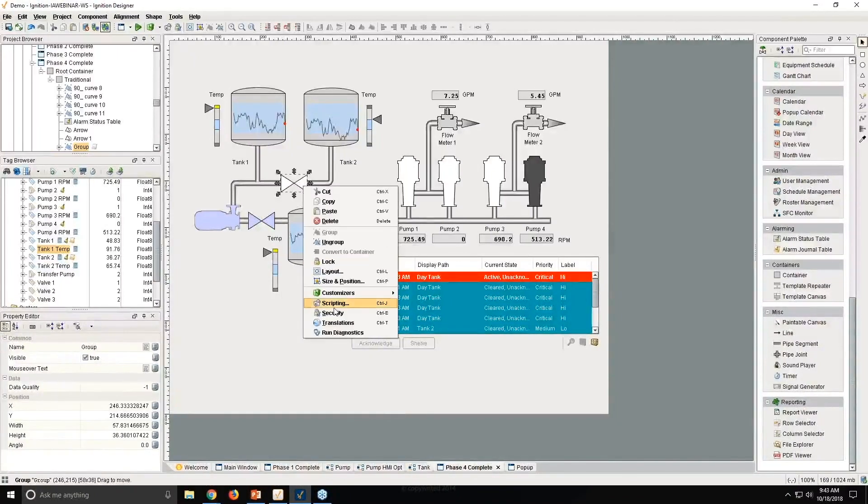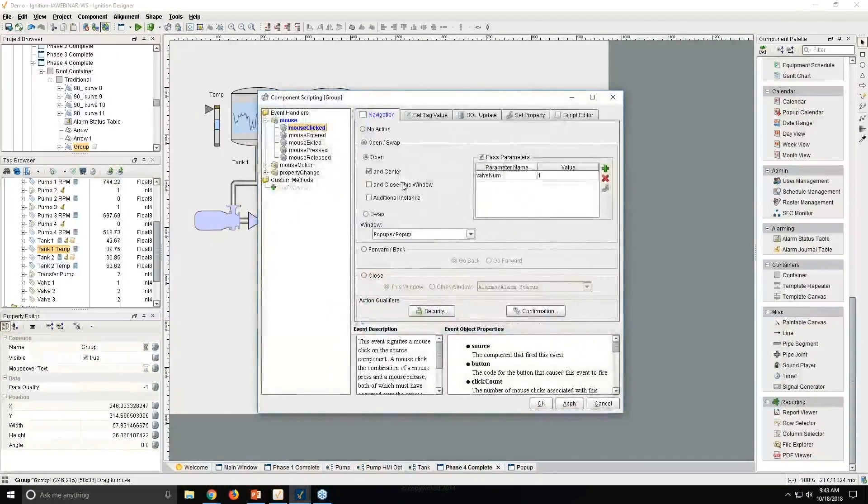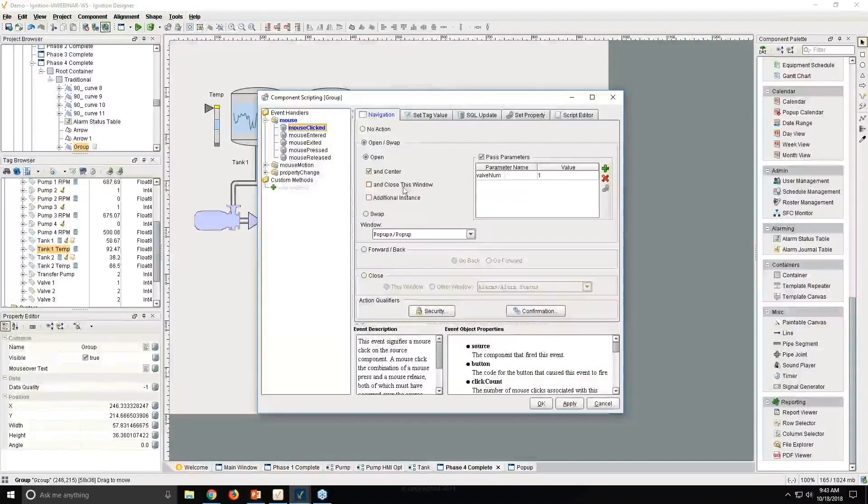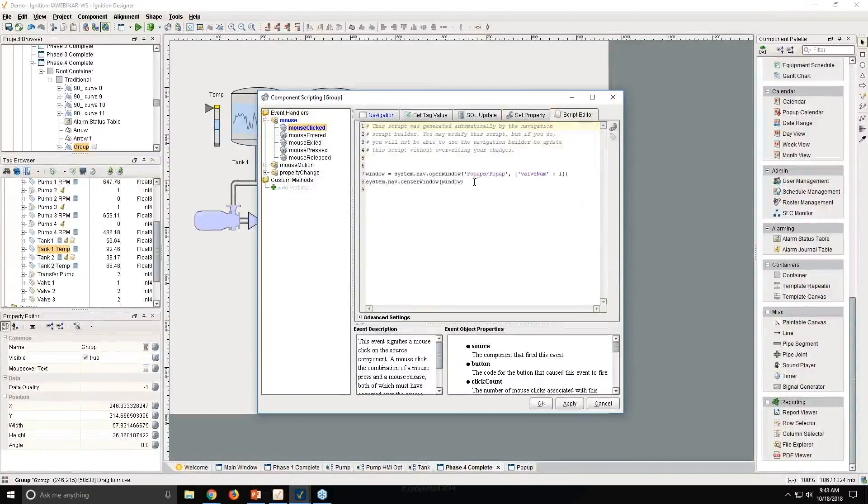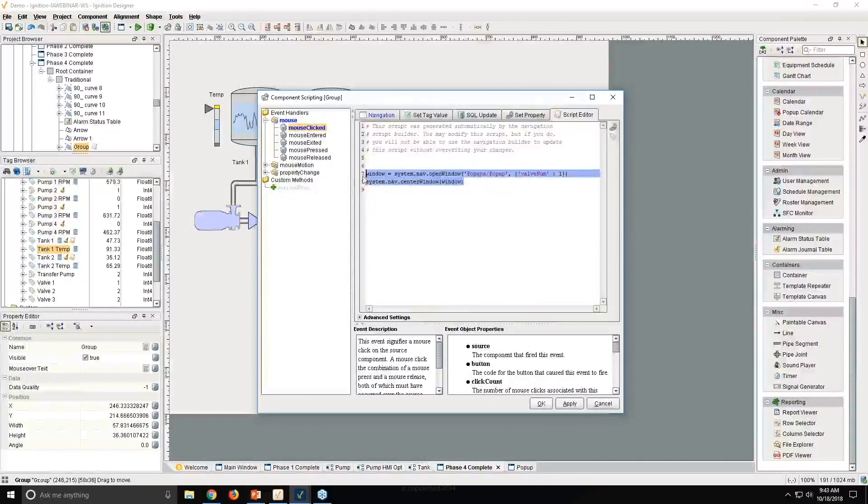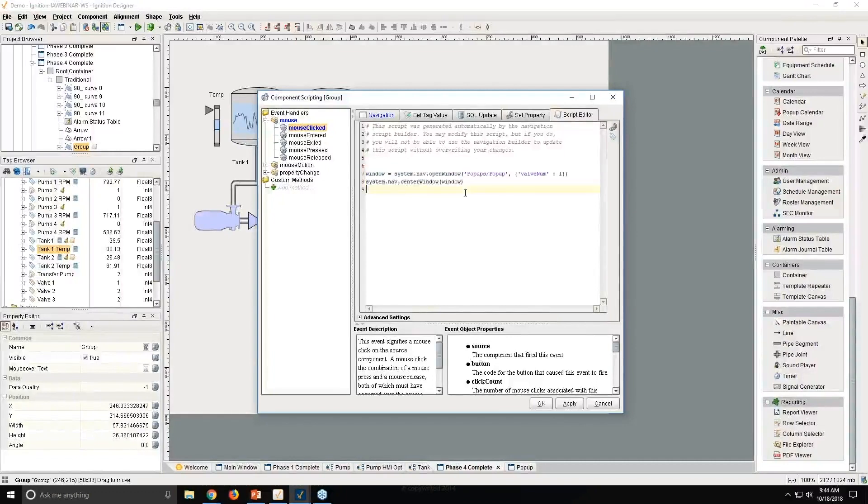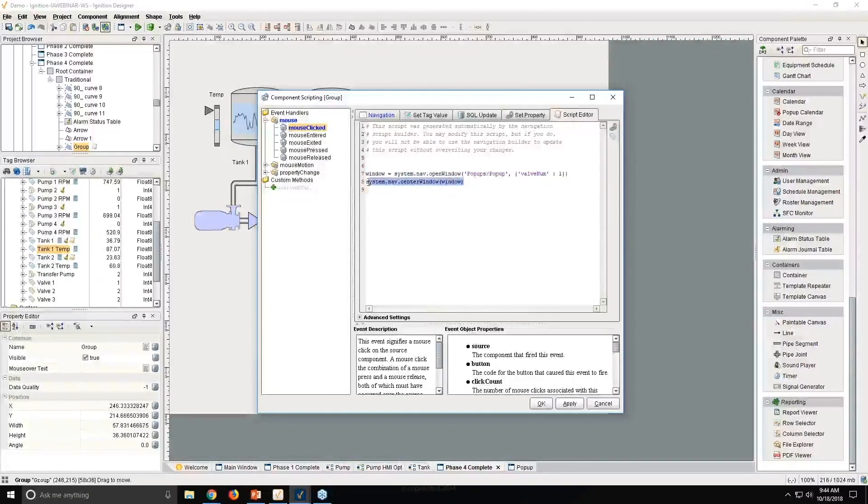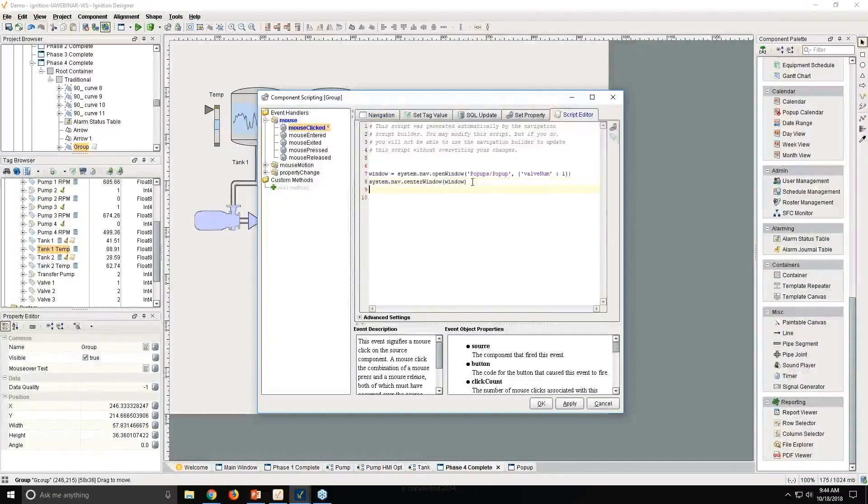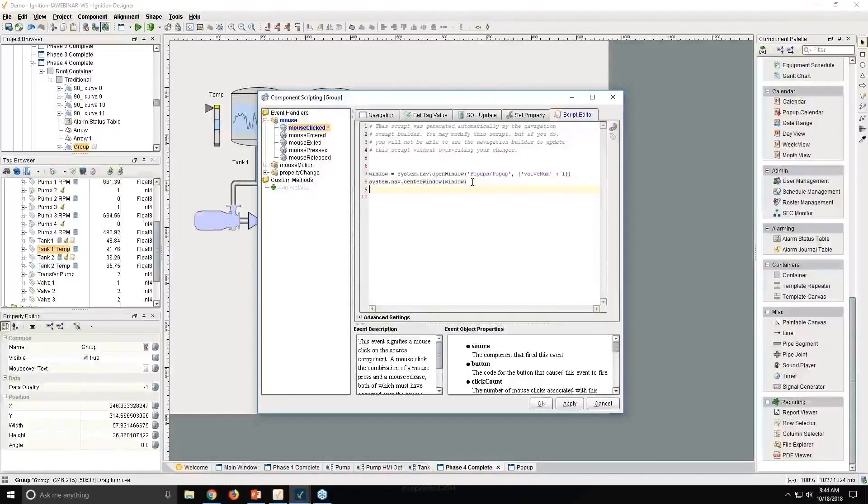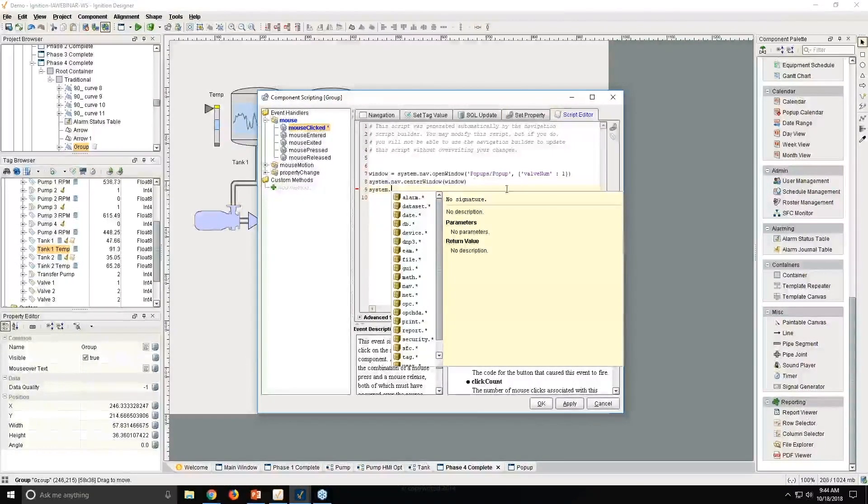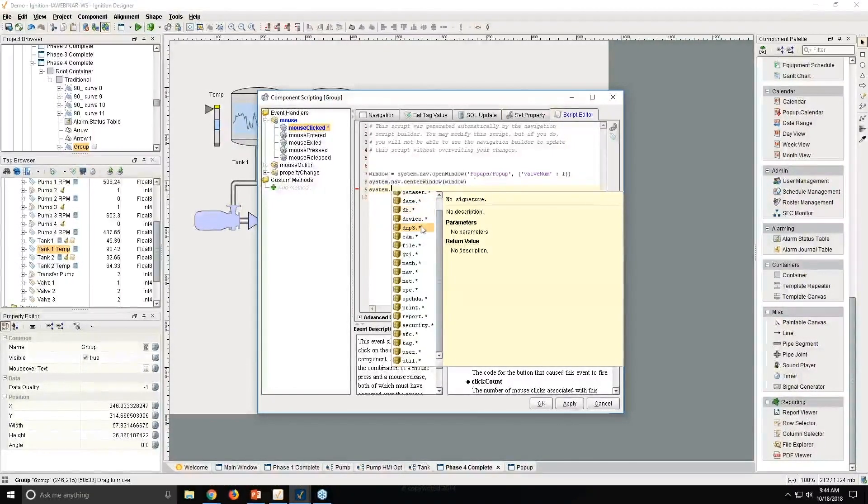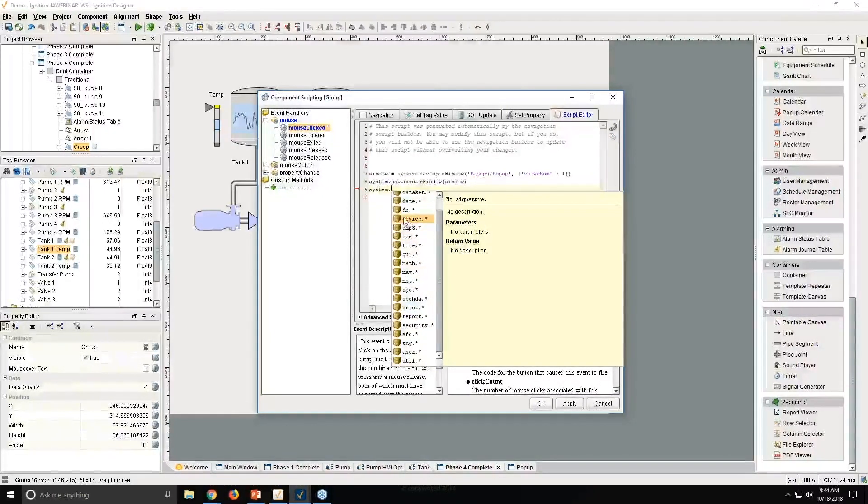But with that, with that scripting, we didn't, you're like, that's not scripting. I didn't see you do any scripting. All you did was click some checkboxes. Well, if you go to the script editor now, you can see that it actually turned those clicks that we did with the mouse into an actual script. And so you can see the Python scripting there. If you wanted to do something more fancy, once again, you could modify this script. I could type in system dot and do control space. And you can see we have all kinds of scripting functions that you could pull in and use here.